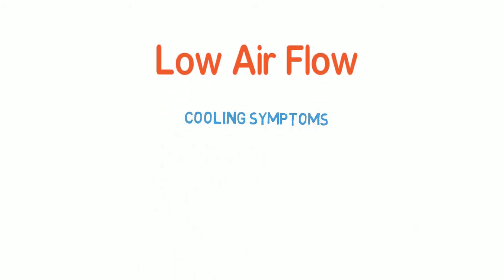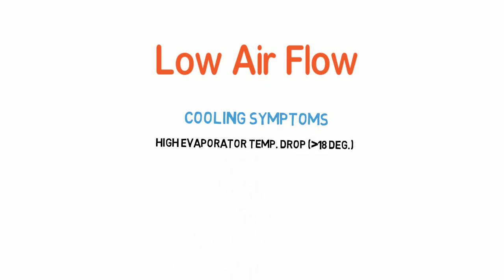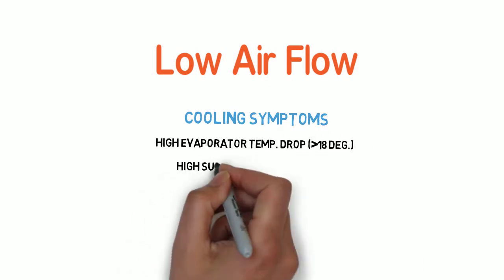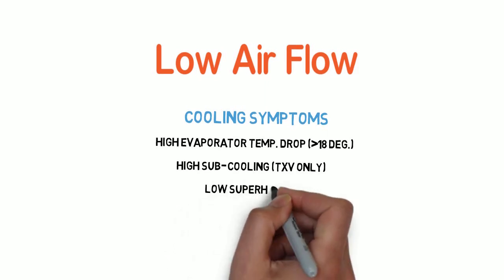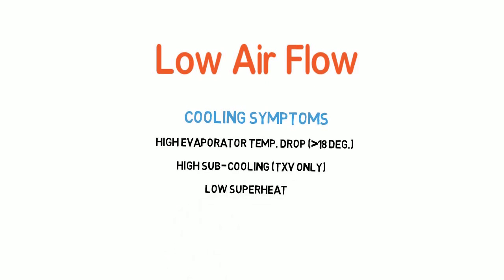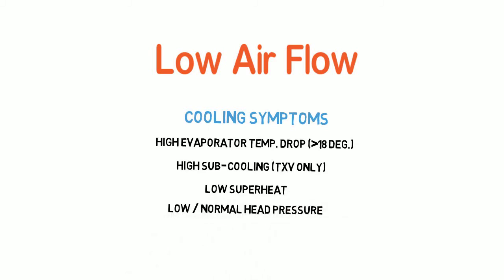Cooling symptoms of low air flow: high evaporator temperature drop over 18 degrees, high sub cooling on TXV equipped units, low superheat, and low to normal head pressure.